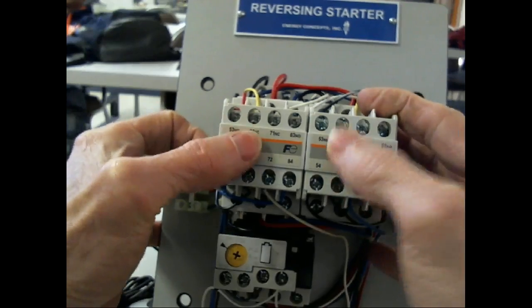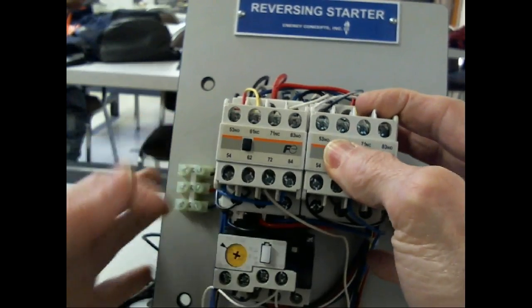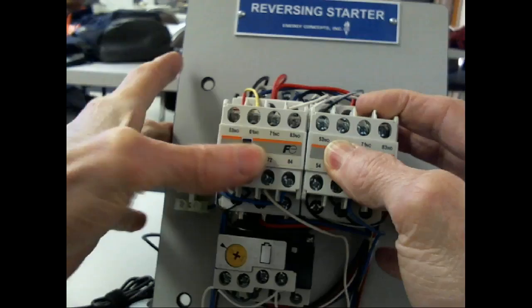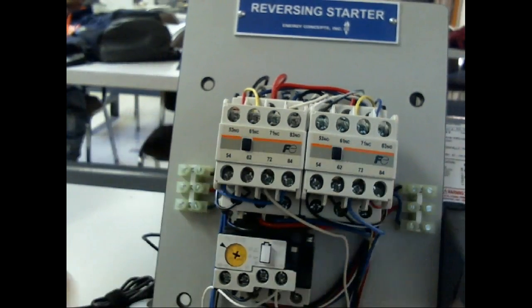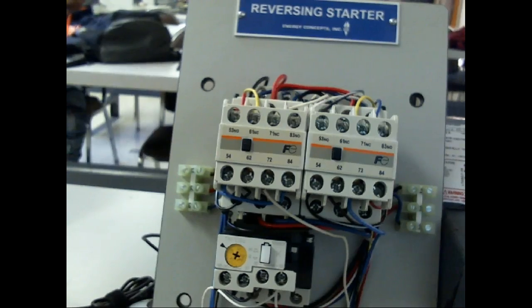So mechanical interlocks means you couldn't do what? Yeah, if you push this one in, you couldn't push that one. But these relays have that manual override on there, and those guys can get you in trouble. So before you push those, you need to understand what's going to happen, because things are going to move, and it's no longer under control of all your safeties, all your limit switches, and everything out there that prevents people from getting killed. You understand? You just lost that feature.